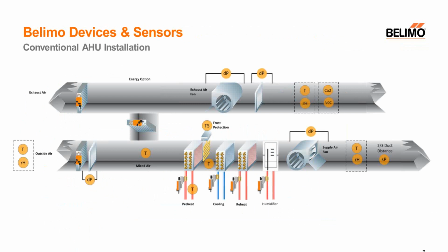And if you zoom out and look at an entire air handler, you can imagine that while there's that one simple process, it's happening all over that air handler. You have multiple valves, multiple damper actuators. You have fans that have speed control on them. Those are all fairly simple processes, but they all have to work together. And there's a digital controller that's connected to every single one of these inputs, and is also providing an output signal to all of those valves and dampers and fans.